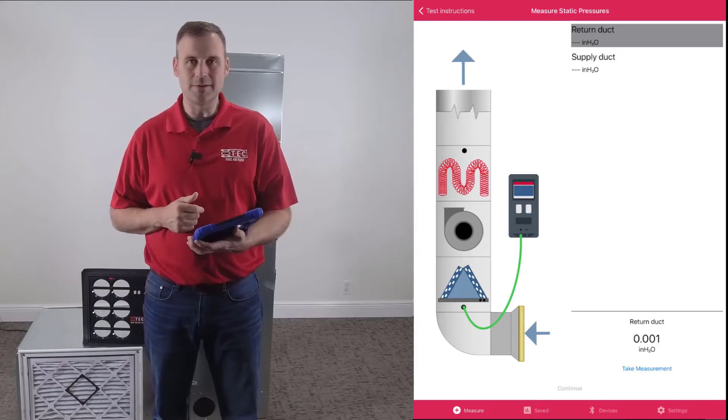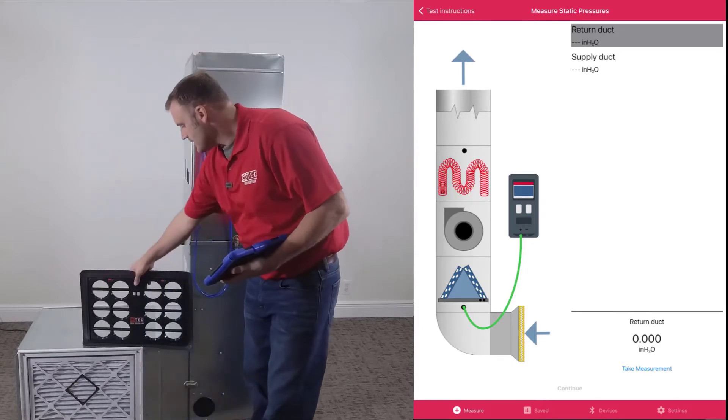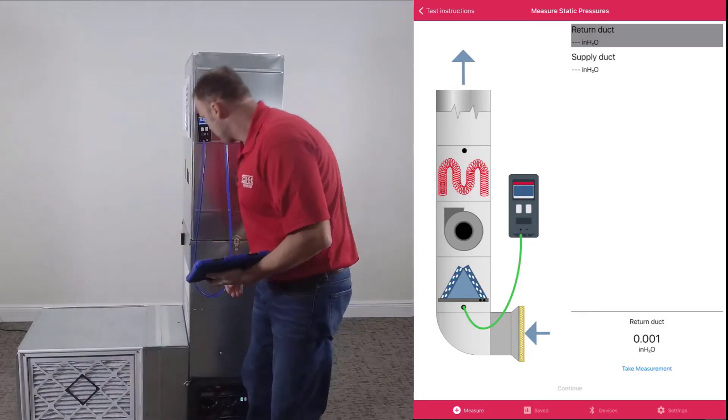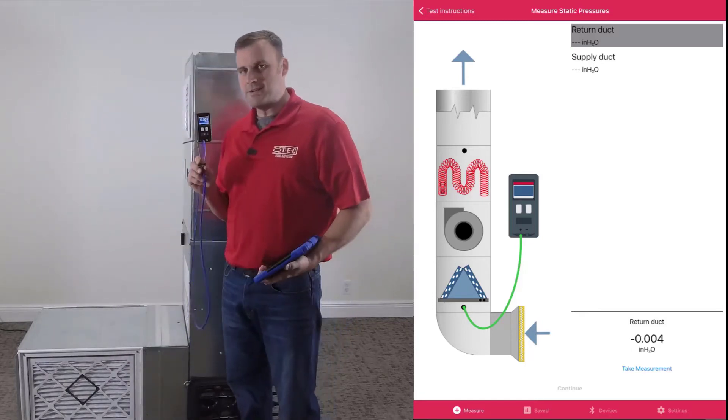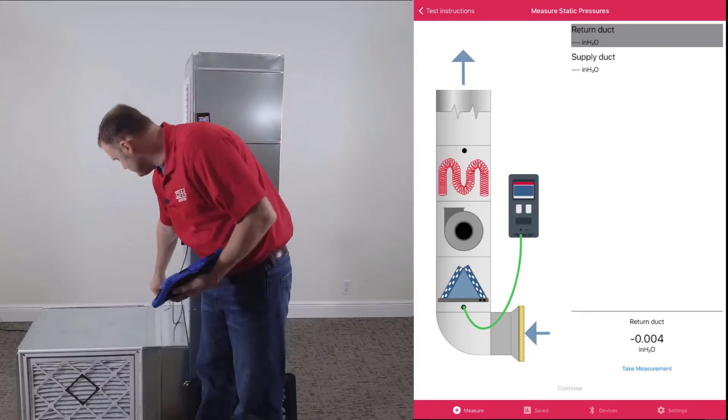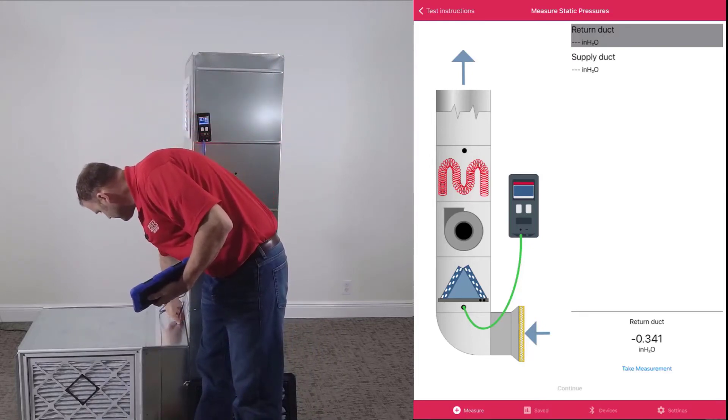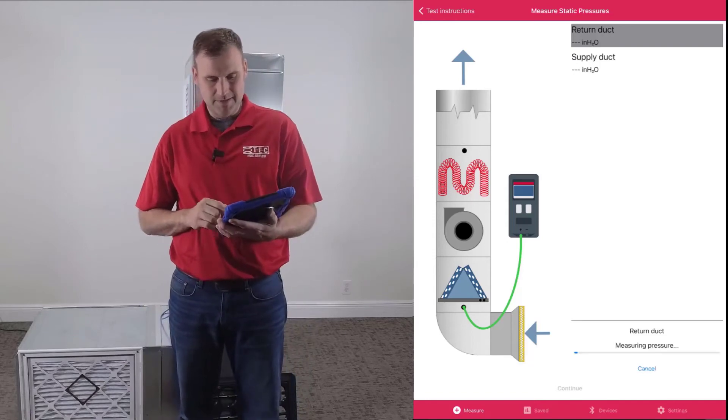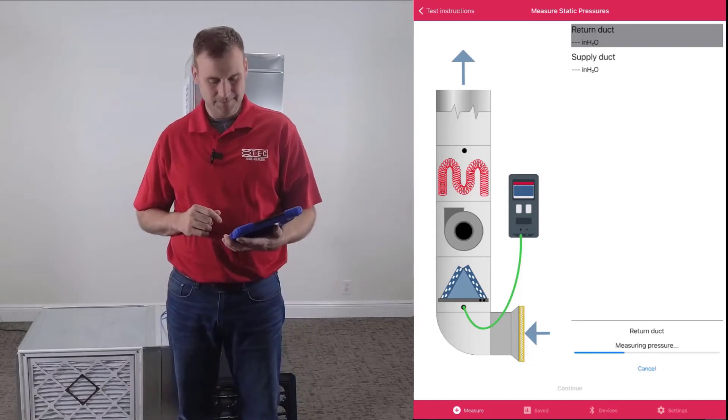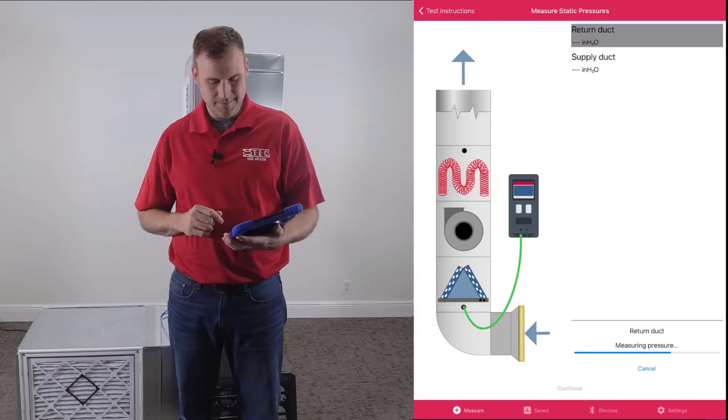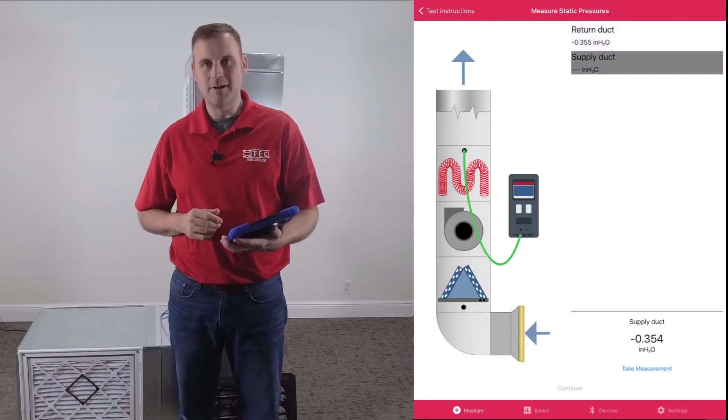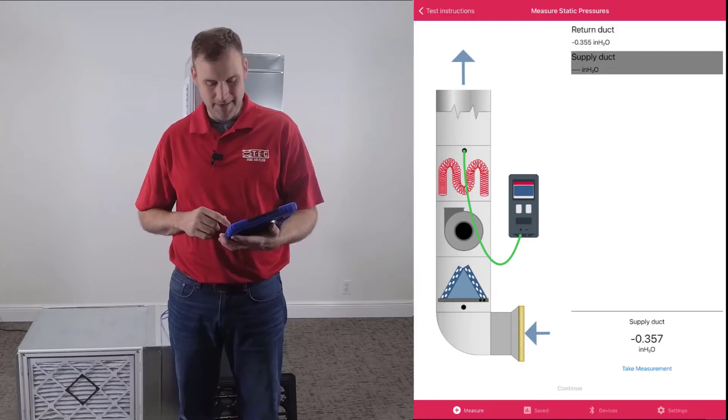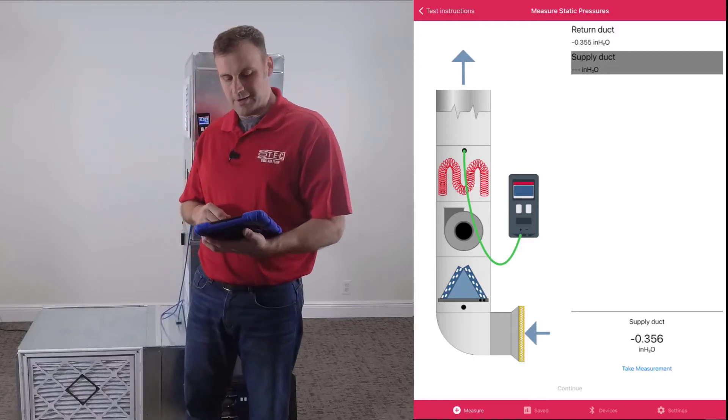You notice it says install the DG8 pressure hose right before the A-coil in the return. Take our static pressure probe. We've got it in the return. Take measurement. Give it a few seconds. We've captured our return static pressure.